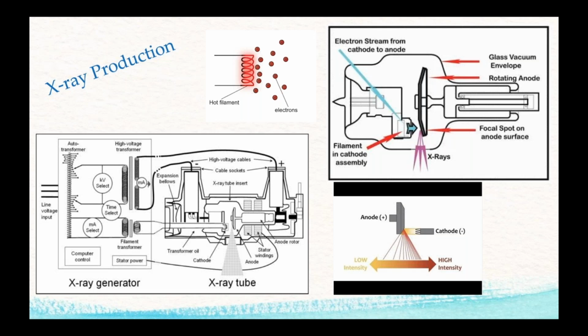And then time. We have lower voltage electronics that are going to control our actual X-ray exposure. To get that high voltage, remember what I said, we're going to go from 380 volts, three phase, or 480 into the hundreds of thousands of volts, 120 kV, 110 kV. So we use a really nice step-up transformer. If you have a typical transformer physics is if you have less windings in the primary and more in the secondary, your voltage is stepped up. If you have the opposite, it steps down. So we use both in the X-ray generator. We step up the voltage, of course, to get our hundreds of thousands of volts. But in our filament, we use a step-down transformer.